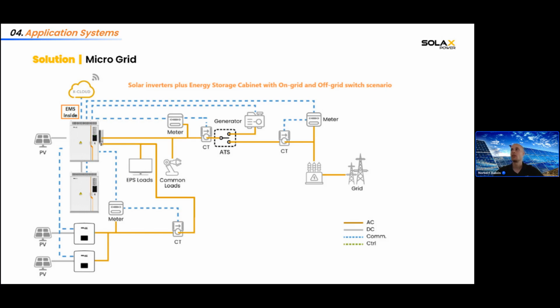What is CT? CT is current transformer. For the meter, you wire the three phases and the zero, and it measures the voltage on the three phases. And the CT is a current transformer that you can connect to each line, and it will measure the amps going through the lines. So with the voltages and the currents, you will have the power for each phase.